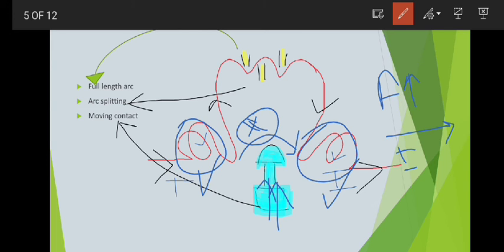because of interruption, those coils are called blowout coils, and the magnetic field does not control and extinguish the arc mode in the breaker, but it moves the arc into the chute. Here is the arc chute. Here the arc is lengthened.